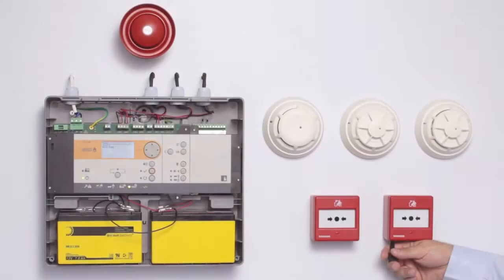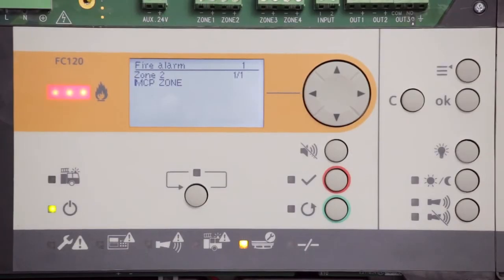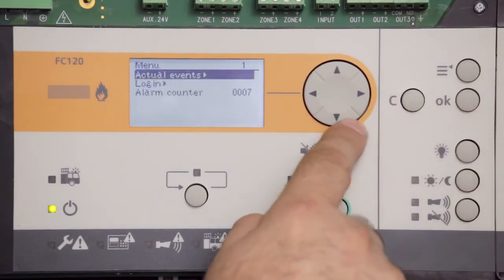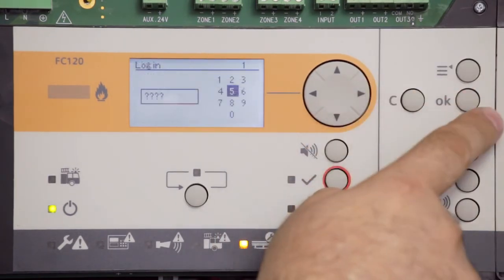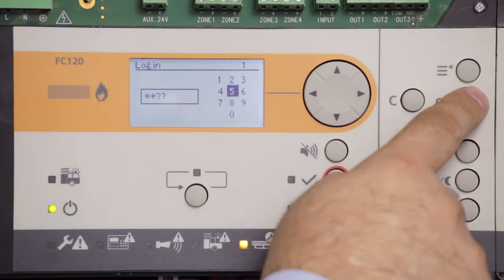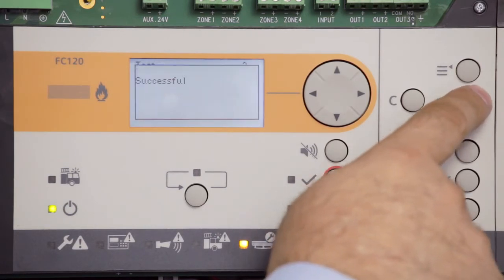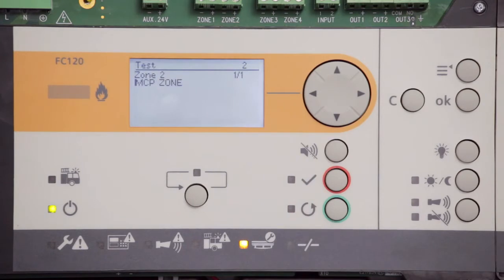How to test a manual call point. Enable test mode for the zone. Depending on the type of call point, insert test key or open the cover to activate. Wait until the LED is on. The sounder sounds for 1 second. Remove the test key or close the cover. The test alarm automatically resets after 15 seconds. Set zone to normal mode operation.